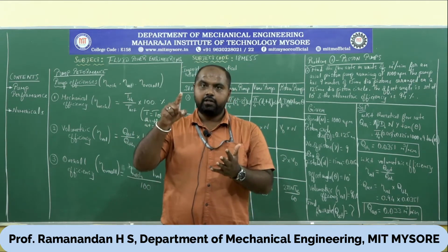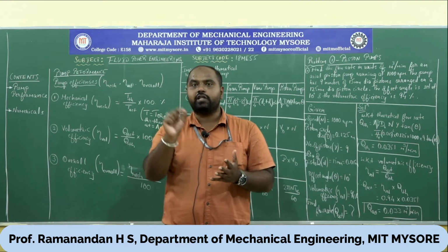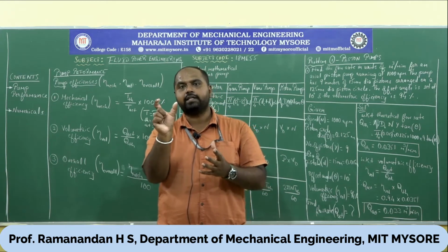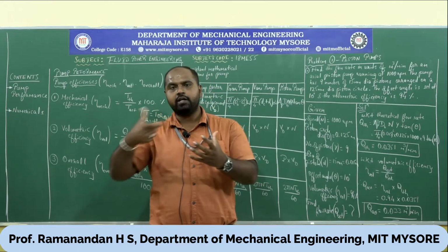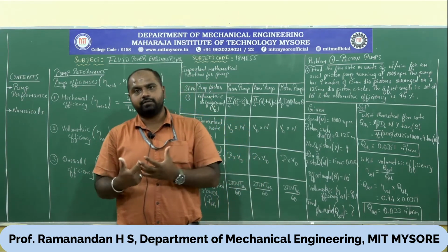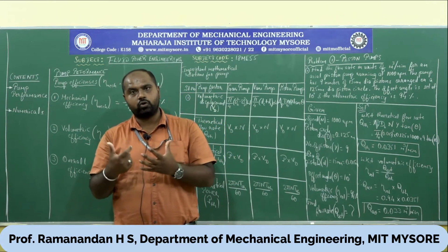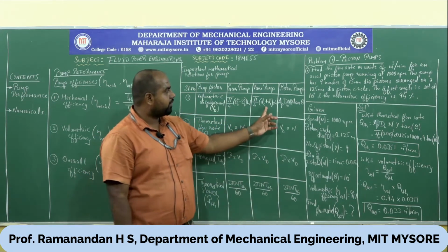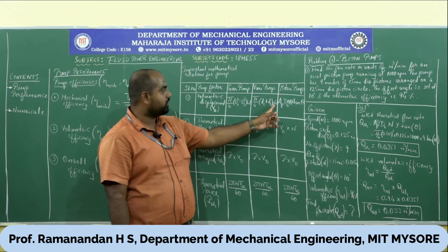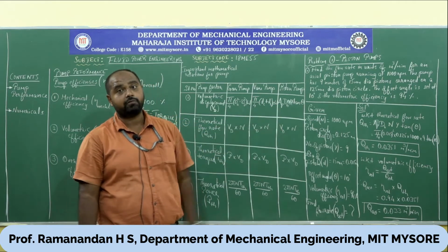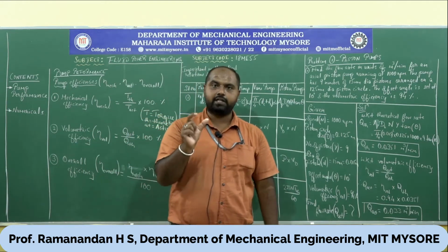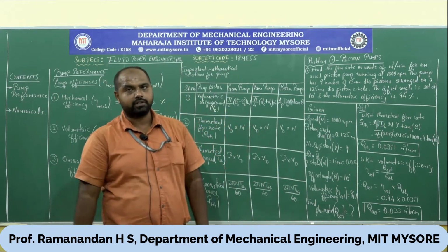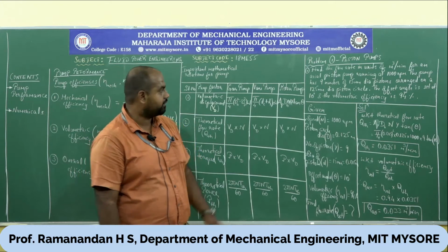The cam ring and the rotor are not concentric, they are eccentric. That eccentricity yields the centrifugal force so that the fluid gets into the vanes of the vane pump. That is the core operating principle. So the formula holds good there: DC plus DR into E into W. W is the width of the vane. The thickness of the vane will decide the amount of fluid trapped in the volume of displacement.